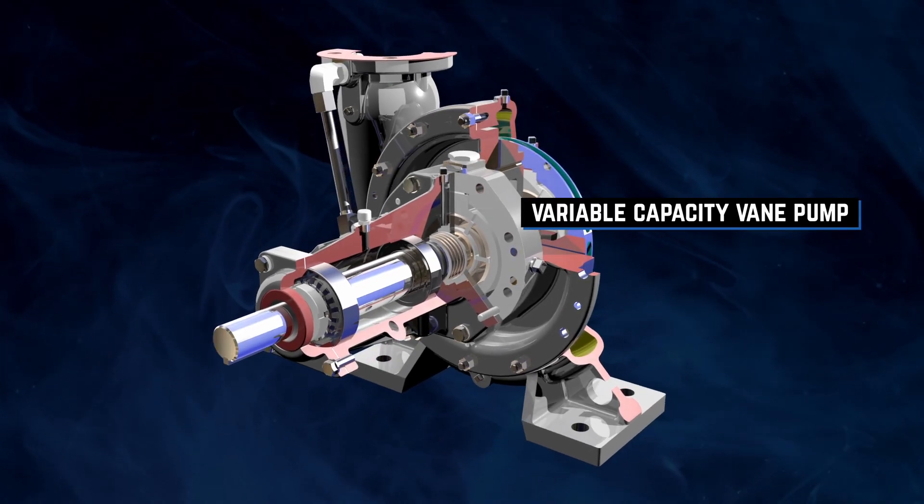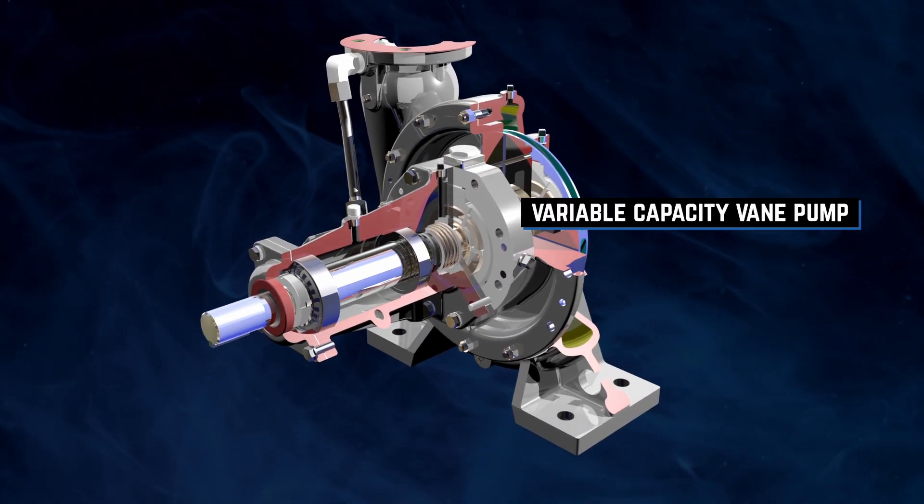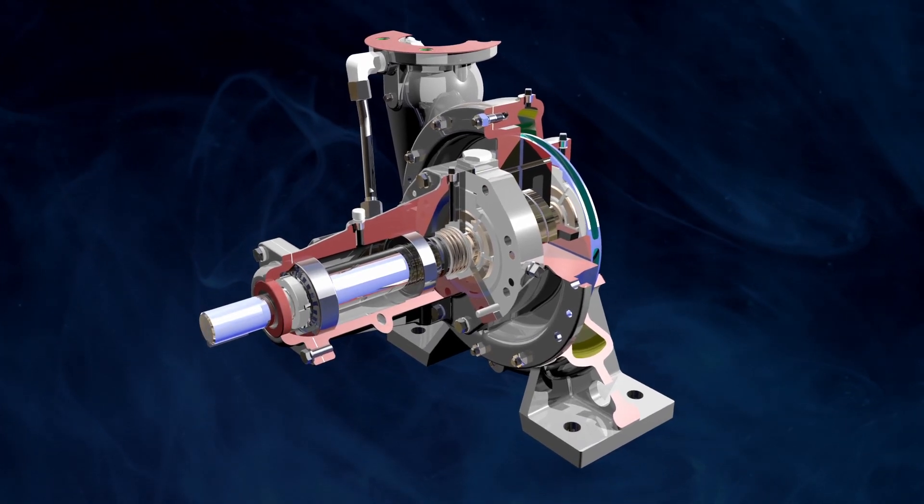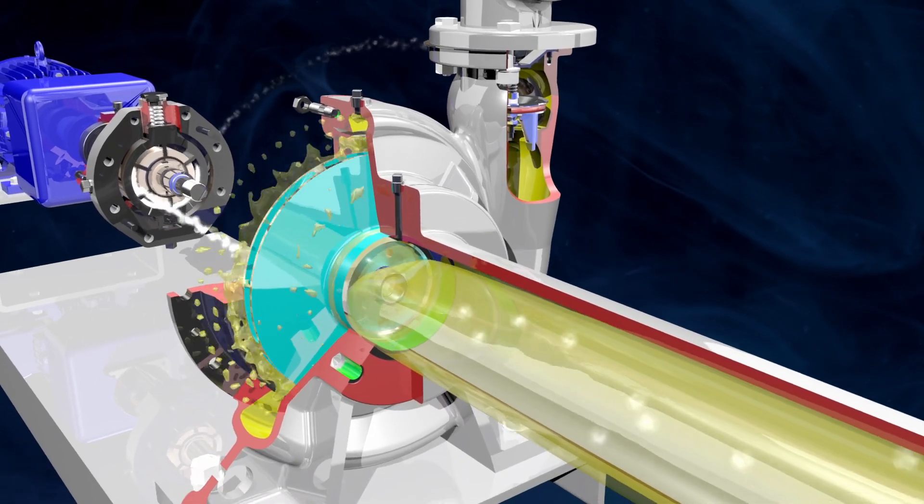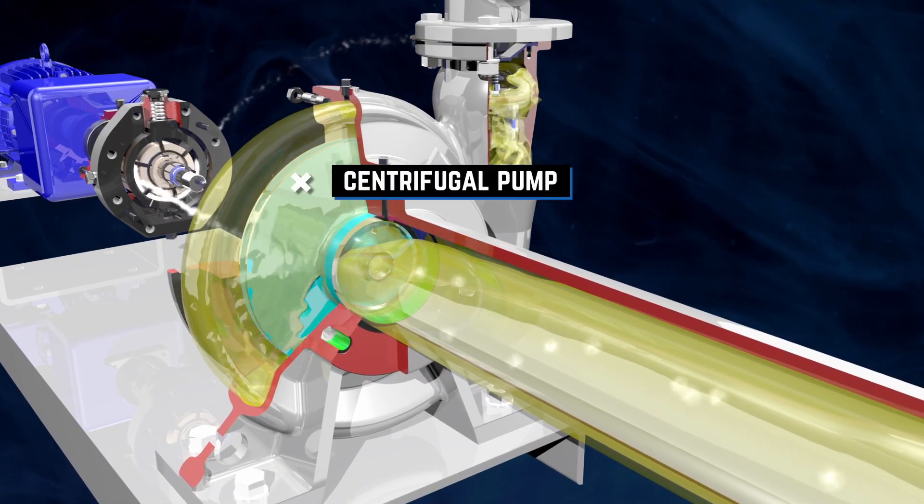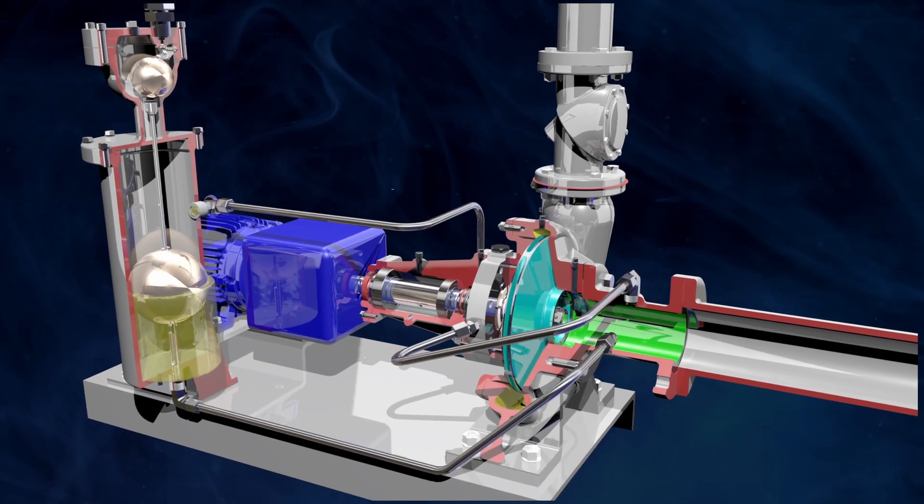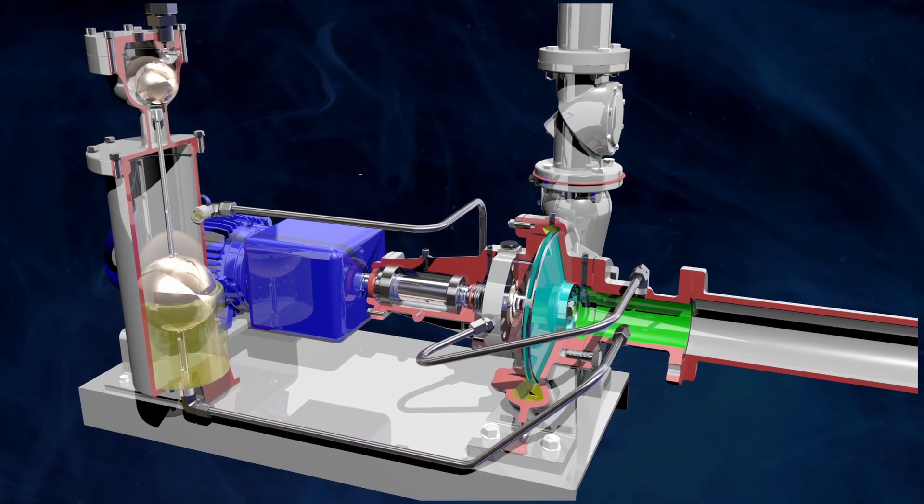A variable capacity vane pump handles the priming cycle, quickly and automatically eliminating air and vapor from the suction line and volute. Once priming is complete, the centrifugal pump takes over, moving liquid efficiently to meet system design requirements.